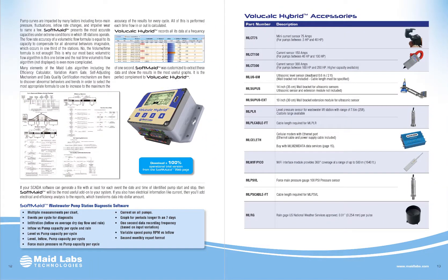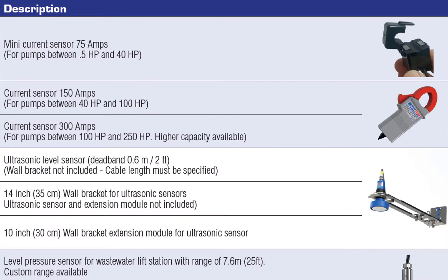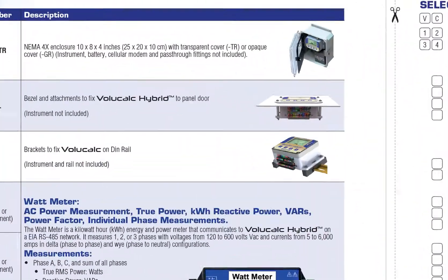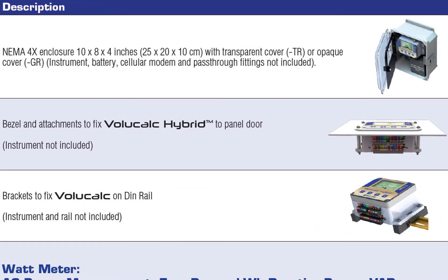A lot of accessories are available for the Volucalc Hybrid. Most of the Volucalc Hybrids we have sold used current clamps to detect when pumps are starting and stopping, along with the actual level sensor already in the lift station. We always suggest using a current isolator when using the local level sensor — this way we're completely disconnected from the system while getting the level information, which also allows us to verify that the level sensor is working properly. There are different ways to install it: in its own panel, screwed to the front door of the control panel, or clipped on the DIN rail.